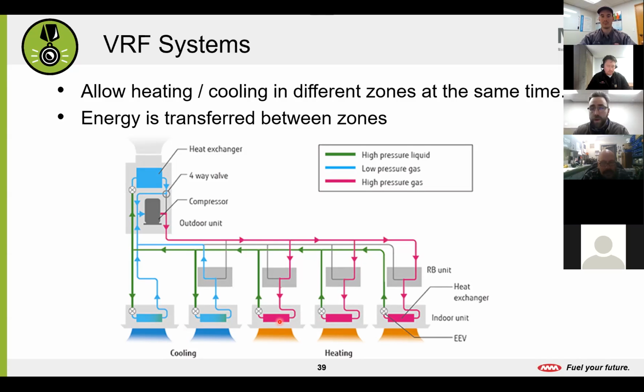The other reason why we have VRF is efficiency. VRF systems are extremely efficient. And the reason for that is on a traditional system, say we're in cooling, right? We looked at our 2 guys on the left here. We're taking heat from our space where we don't want it. And on a traditional system, we would then move it to our outdoor unit where we get rid of it. We have to reject it, right? What VRF allows us to do is to not only move that heat from inside to outdoors or vice versa, but also between zones. So if we take a look at the system here, we have 2 zones on the left in cooling. We have 3 zones on the right in heating.